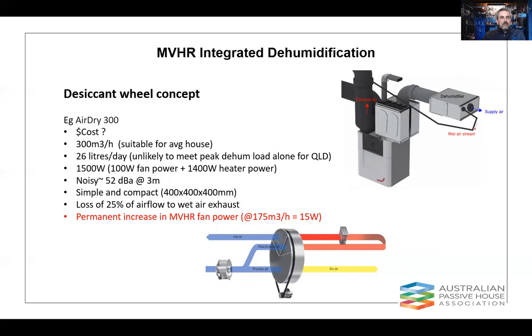We find dehumidification levels around about 26 litres per day. That might not be enough still to meet your peak load for Queensland, so you need to be careful there. They do have reasonable power consumption. This particular model that'll do 300 cubic metres per hour is about 1500 watts, so not insignificant.